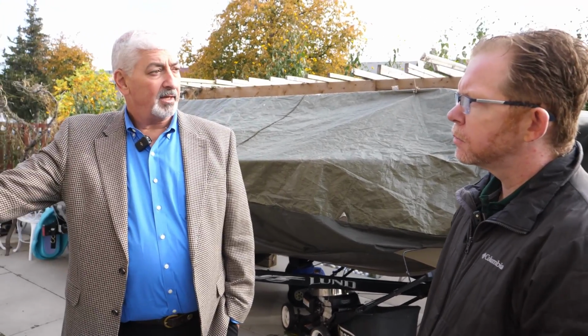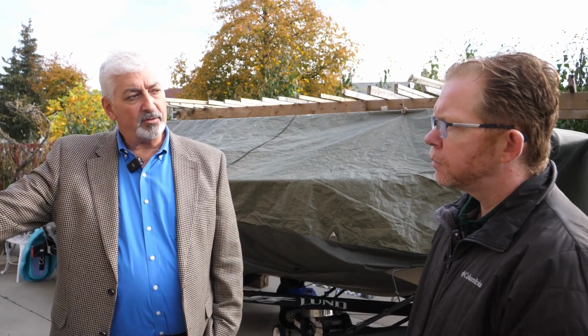When this comes in and replaces an indoor furnace, you can seal back the openings for the flue from that furnace. If they take the optional domestic hot water storage tank at the same time, they can take out their atmospheric or their power vented gas water heater and seal up those connections as well. So the only thing you're bringing into the house with this unit is 2 1-inch pipes, PEX, oxygen barrier PEX, or copper, and that 140-degree hydronic fluid is what's accomplishing the heat exchange inside in the air handler as well as the indirect storage tank.